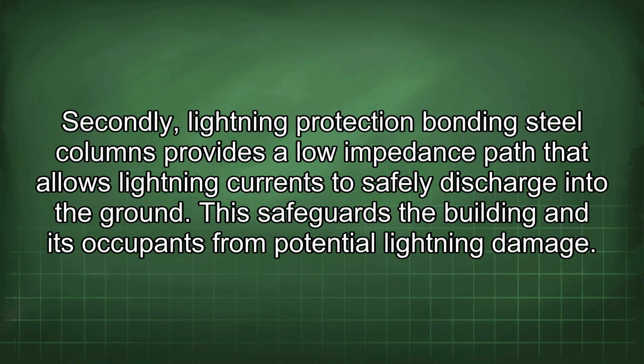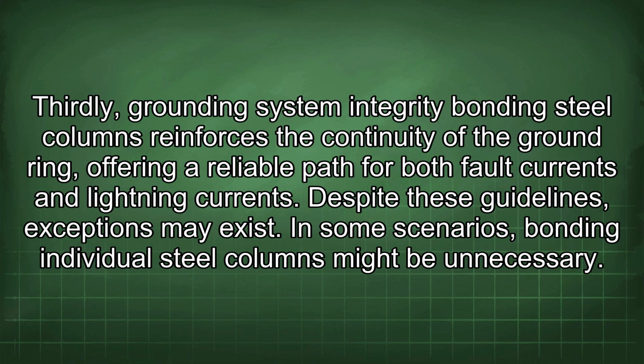Secondly, lightning protection. Bonding steel columns provide a low impedance path that allows lightning currents to safely discharge into the ground. This safeguards the building and its occupants from potential lightning damage. Thirdly, grounding system integrity. Bonding steel columns reinforces the continuity of the ground ring, offering a reliable path for both fault currents and lightning currents.